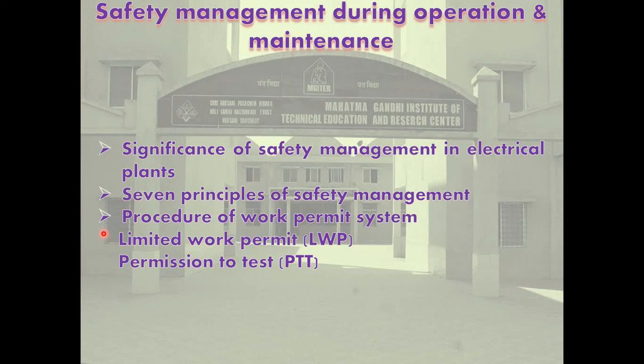Work permit system, first, is for safety of personnel and plant. A work permit on a standard form is issued by an issuing authority, like commissioning managers, site managers, plant managers, to the permit holder for specific work in a specific zone for a specified period. The specific zone is disconnected from the rest of the system by opening all the incoming and outgoing circuits and isolators, and other things, which are then locked, and the safety interlock keys are retained by the issuing authority.